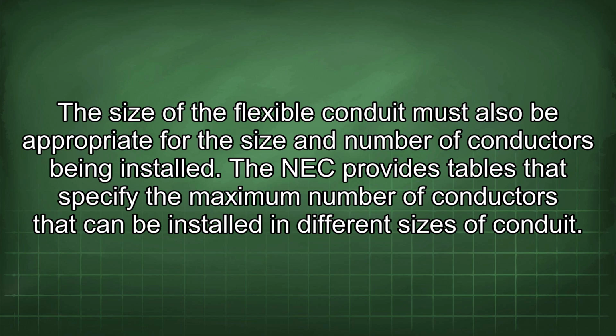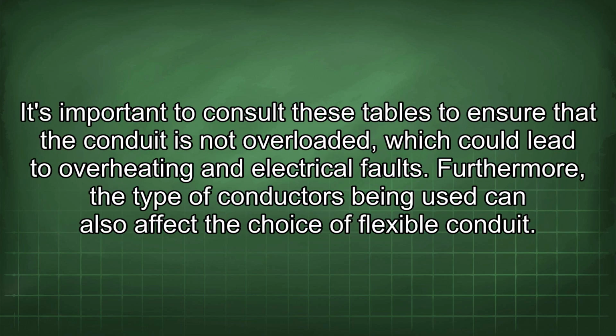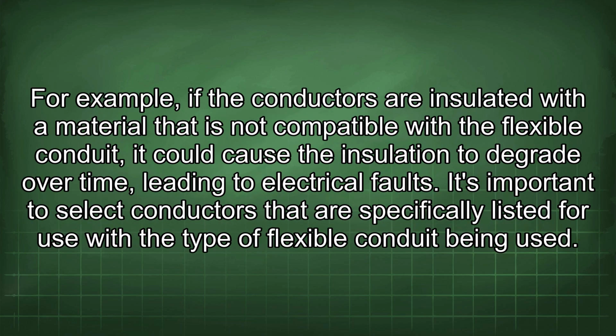installed. The NEC provides tables that specify the maximum number of conductors that can be installed in different sizes of conduit. It's important to consult these tables to ensure that the conduit is not overloaded, which could lead to overheating and electrical faults. Furthermore, the type of conductors being used can also affect the choice of flexible conduit. For example, if the conductors are insulated with a material that is not compatible with the flexible conduit, it could cause the insulation to degrade over time, leading to electrical faults. It's important to select conductors that are specifically listed for use with the type of flexible conduit being used.